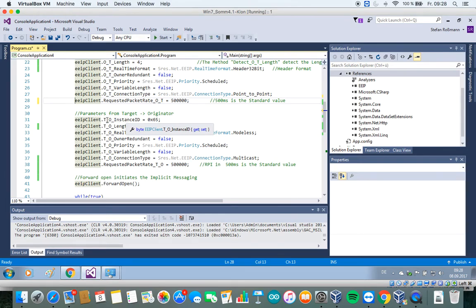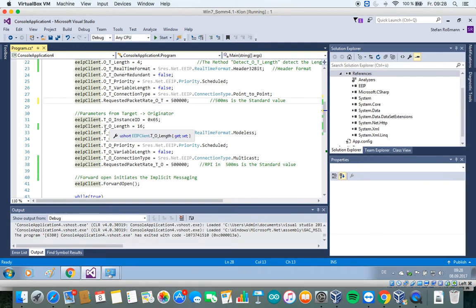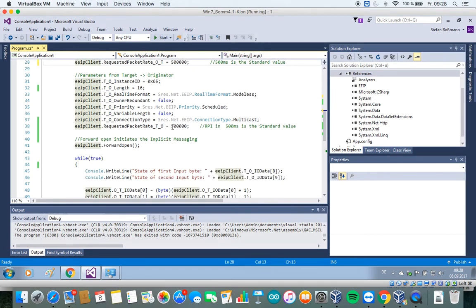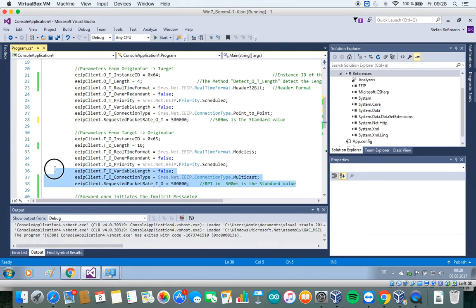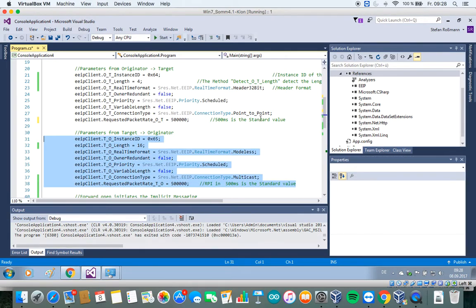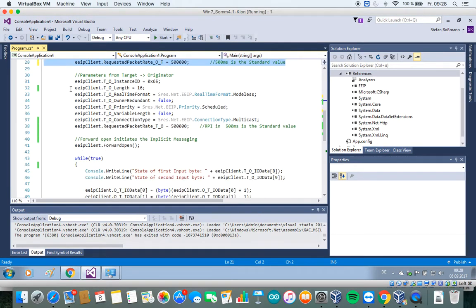The same parameters we have to define for the direction from the target to the originator. That means from the point IO device, in our case, or from the Ethernet IP device, to the .NET application. So these are the parameters necessary from the target to the originator, and these from the originator to the target.